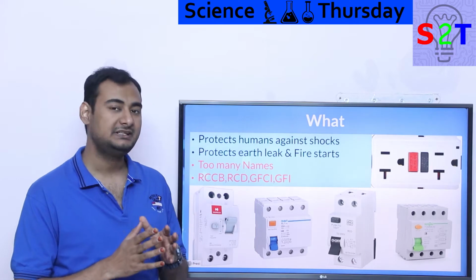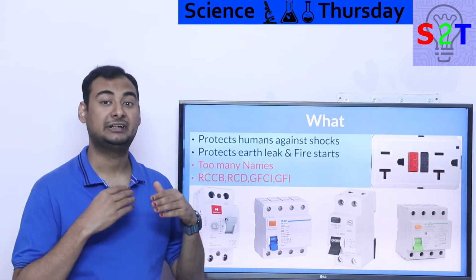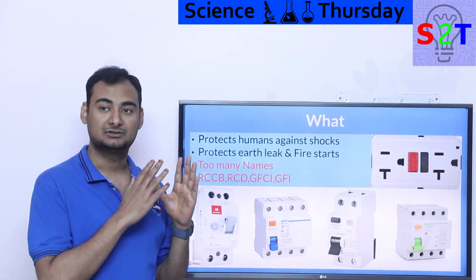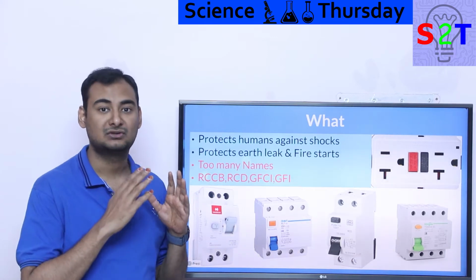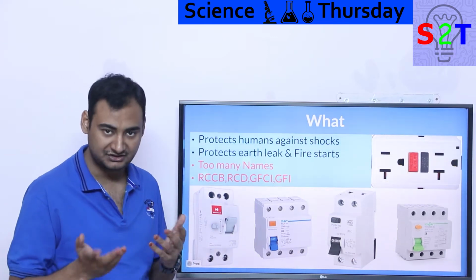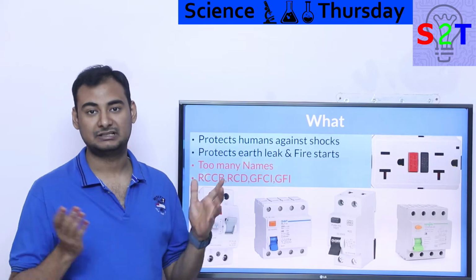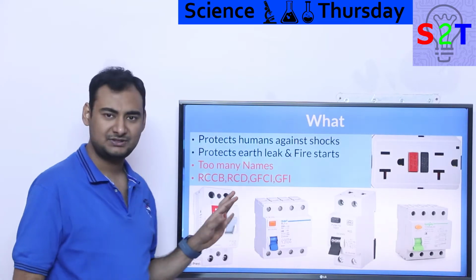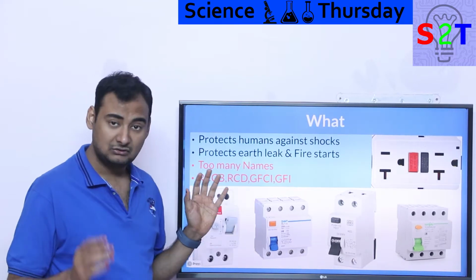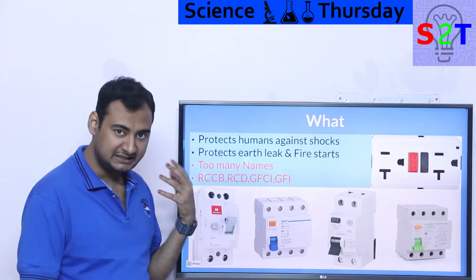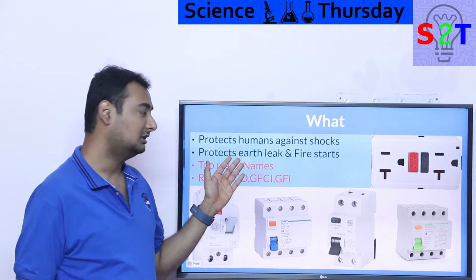For example, an MCB's primary job is to make sure we do not have any overcurrent event. A surge protector's primary job is to make sure we do not have any overvoltage events, surges. And this puppy's job is to make sure that we don't get electrocuted. So this puppy is one of the most sensitive ones. Now, this also has secondary benefits because inherently what it's doing is detecting earth leakage.